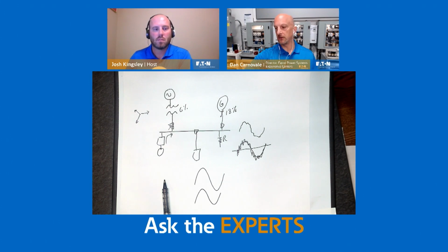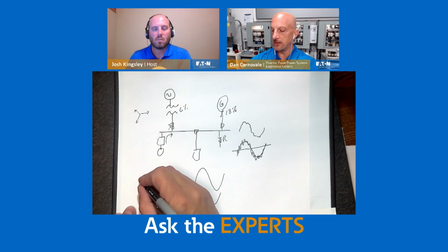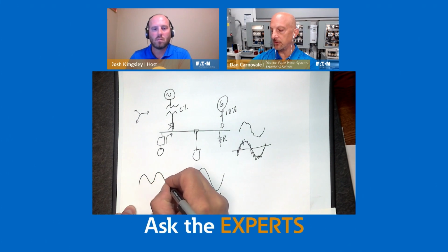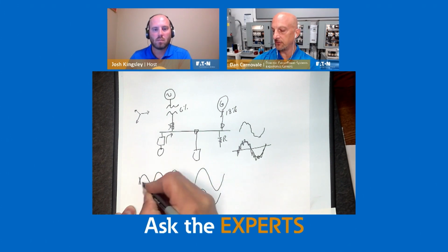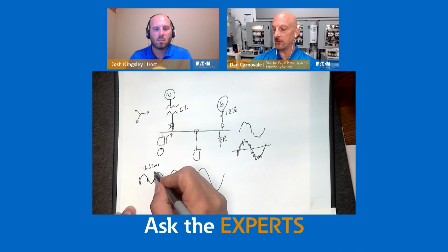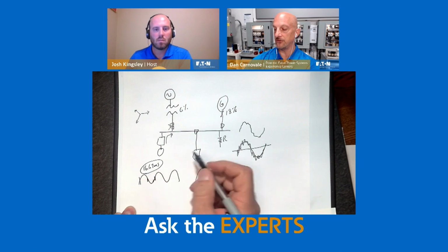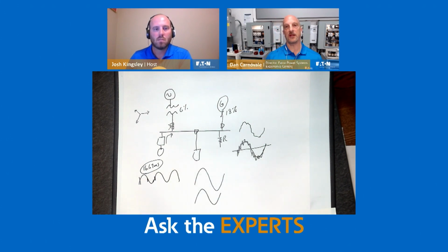They were counting. A nice way to keep track of time, by the way, is if you're looking at a sine wave, every time it crosses zero here and then back here again, that happens to be 16.67 milliseconds. Well, if it crossed there and here and maybe over here again, now every time it crosses zero, it thinks that's 16.67 milliseconds. So the welding line that was supposed to be 20 times that was only getting 8 times that. They were having bad welds and stuff.